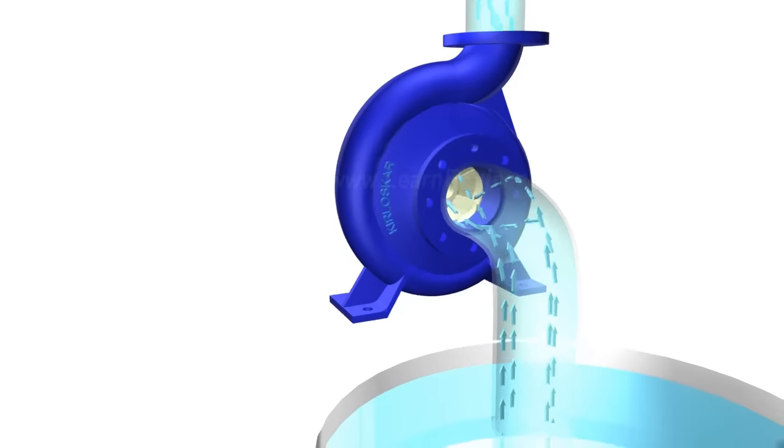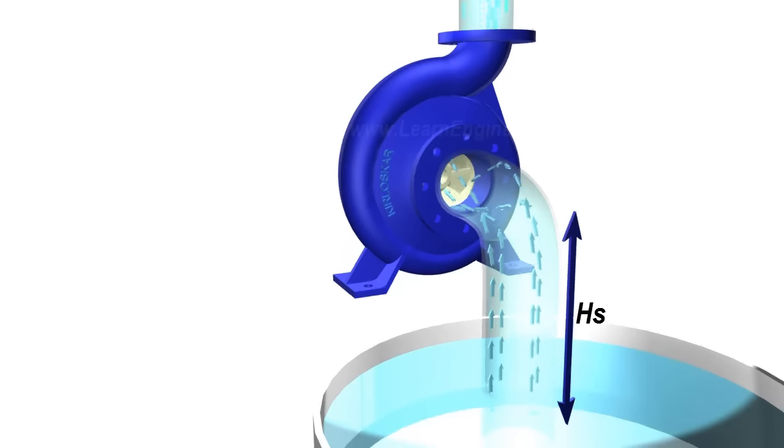More the suction head, lesser should be the pressure at the suction side to lift water. This fact puts a limit to maximum suction head a pump can have. Careful pump selection is required to avoid the problem of cavitation.